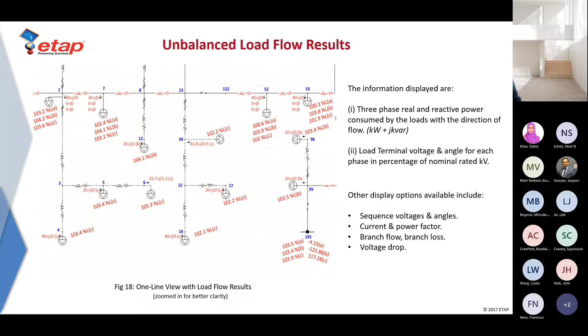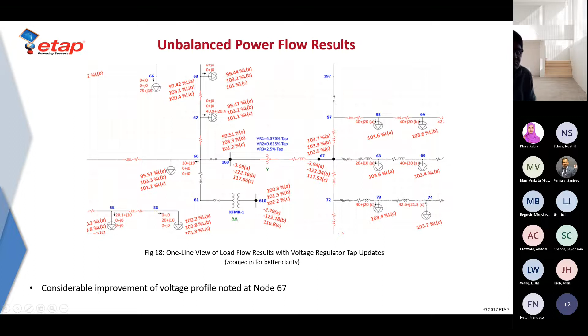This is another screenshot of the unbalanced load flow results, but with the voltage regulator in place, so that you can see how that is displayed and the impact of the voltage regulator. The tap settings are 4.375%, 0.625%, 2.5%. What is also obvious is that the voltage regulator works as expected, because if you see the ends of the two buses, 160 and, sorry, 67, you can see that 67 is a little more balanced and the voltage profile is a little better than 160. So this voltage regulator helps balance things out and keep things good.